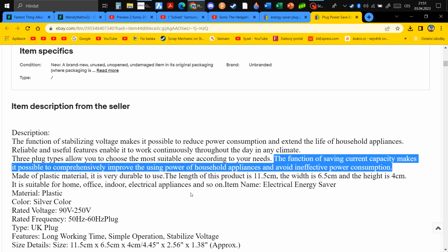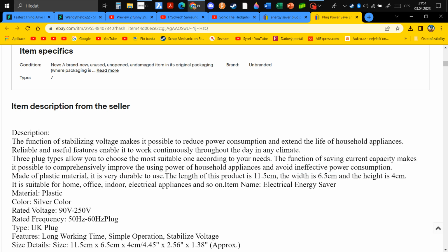So yes, that's bullshit, because you have to be drawing quite a bad power factor in order to make use of it. In a factory it would make sense, because they'd have a lot of power factor correction capacitors, since they have a large number of motors. But in a household, where most appliances now have power factor correction inbuilt, it just doesn't make sense.